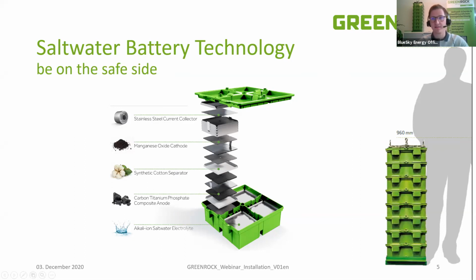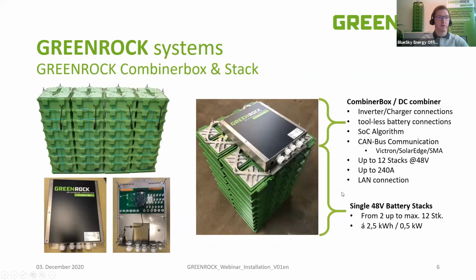This stack can be used first in 48 volt systems, what we call the GreenRock Stack plus Combiner Box. The Combiner Box can be compared to a plus and minus copper bus bar - inside it, as you can see here, you can connect up to 12 of these battery stacks, with one stack at 48 volts and all the others connected in parallel to each other.